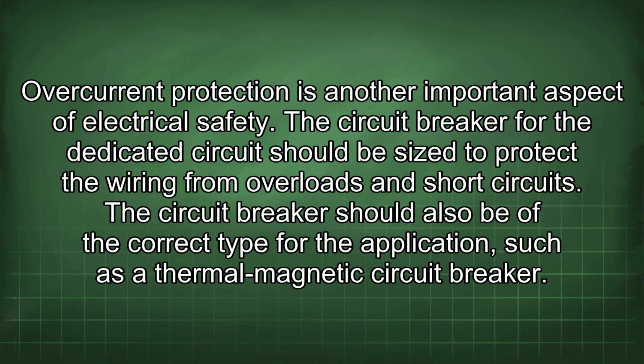Overcurrent protection is another important aspect of electrical safety. The circuit breaker for the dedicated circuit should be sized to protect the wiring from overloads and short circuits, and should be of the correct type for the application, such as a thermal-magnetic circuit breaker.